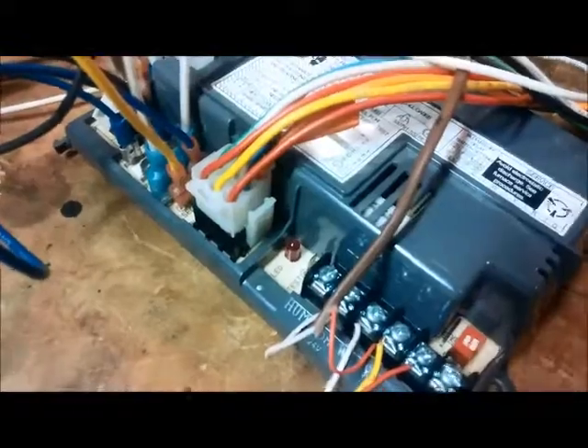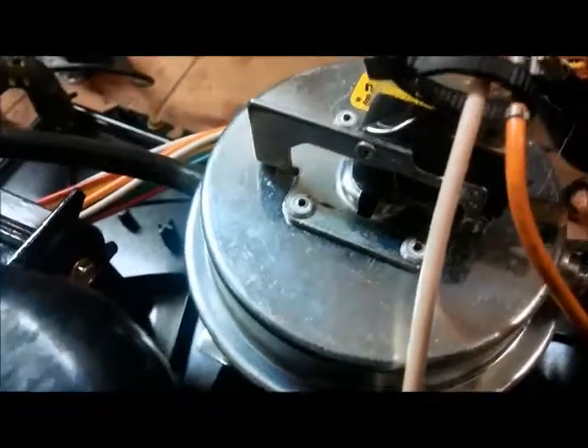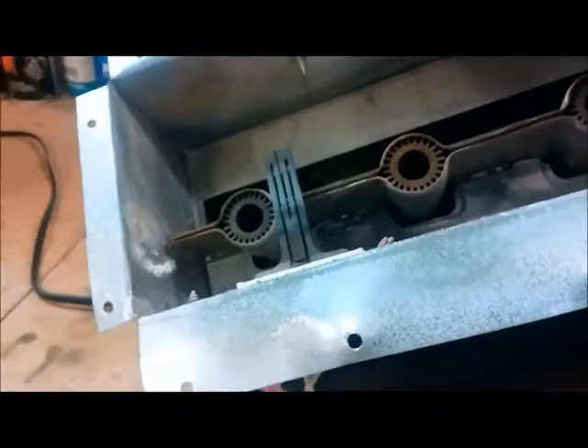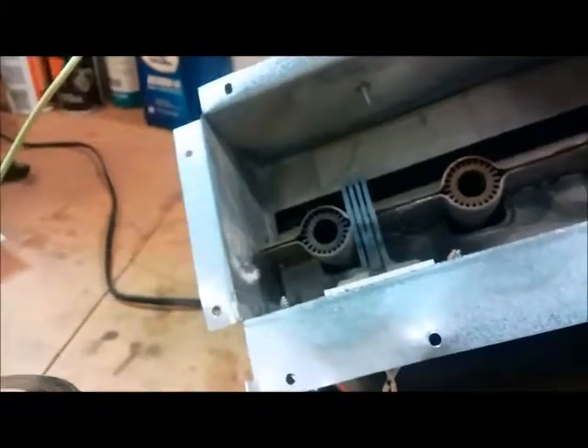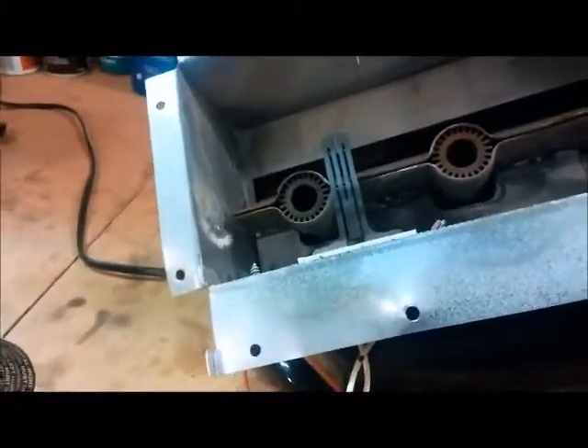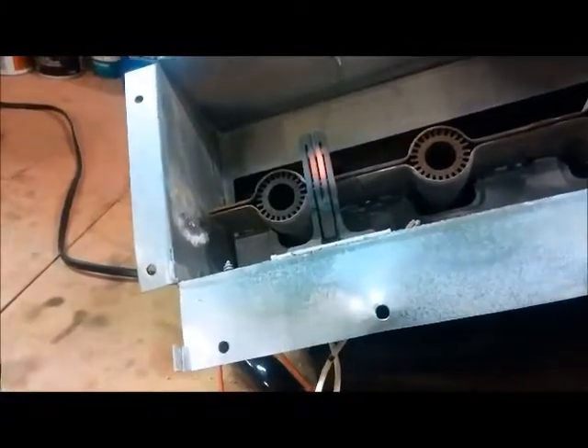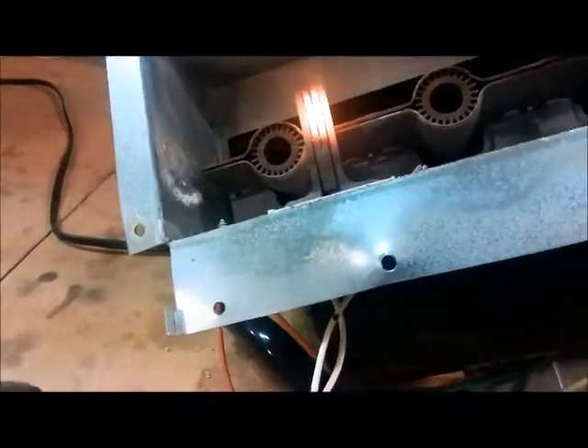Okay, so we're getting our 3-1. Say we close the pressure switch manually by just jumping these two wires, which is what happens when the inducer runs. Now we're going to lose that fault code. The inducer should be running right now. And then our igniter is going to start to glow shortly here. And I just heard the relay closed. It's sending power to the igniter. It's probably going to glow for 20 seconds or so typically.